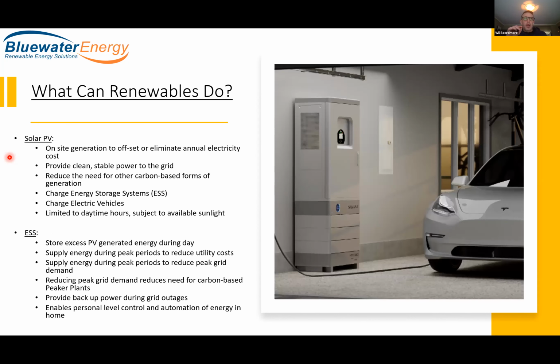Unfortunately, PV and batteries don't deduct from that total load calculation, although we can supplement or even completely offset grid-supplied electricity consumption with renewables. It doesn't change the fact that the loads are the loads. But there is something else we can do to manage that, and we're actually trying to achieve this with a project right now, where the homeowner has been told he needs to go to 400 amps. We're in discussions with the ESA now, and I'll speak about that in a minute.